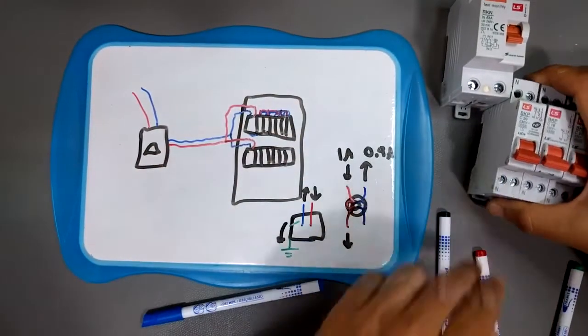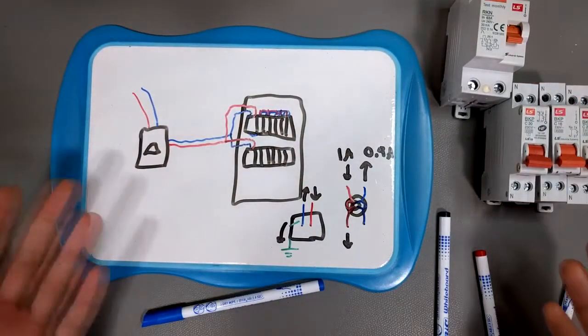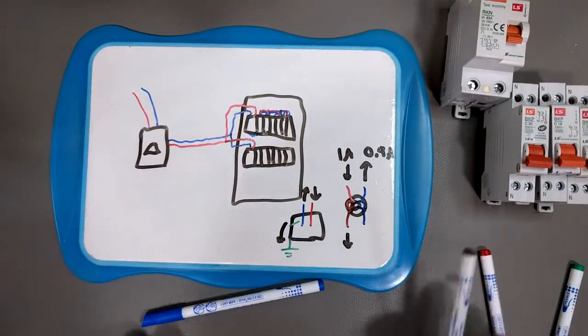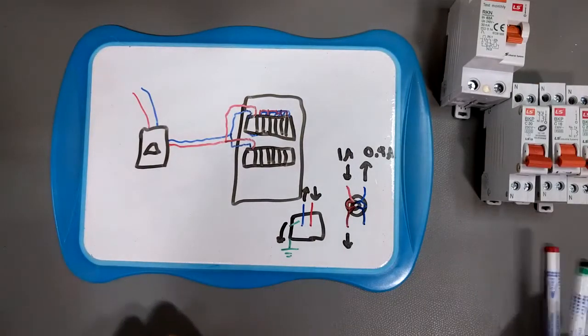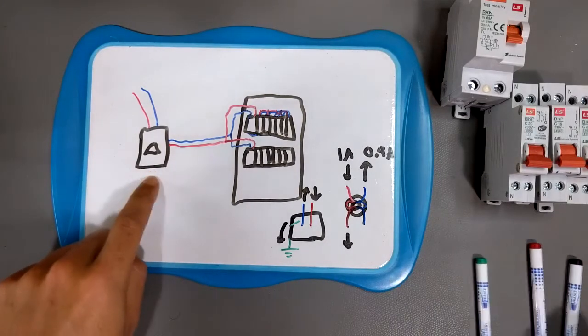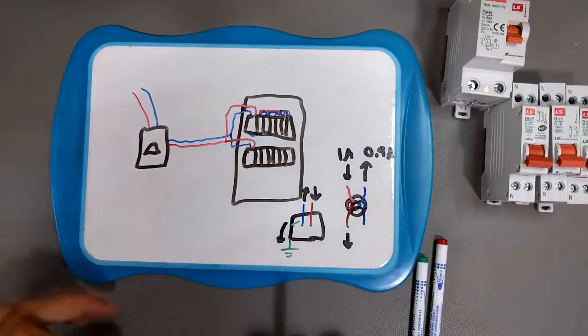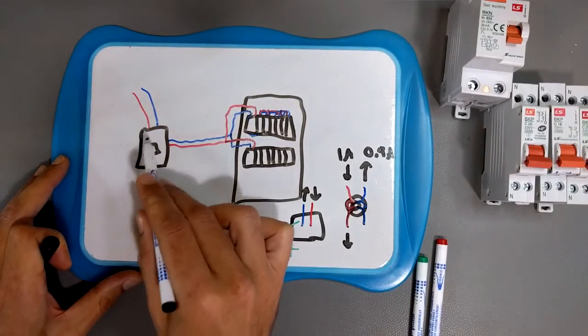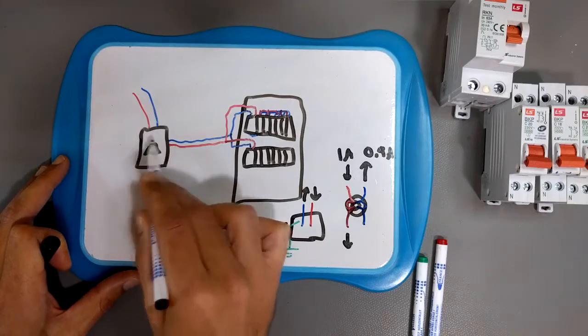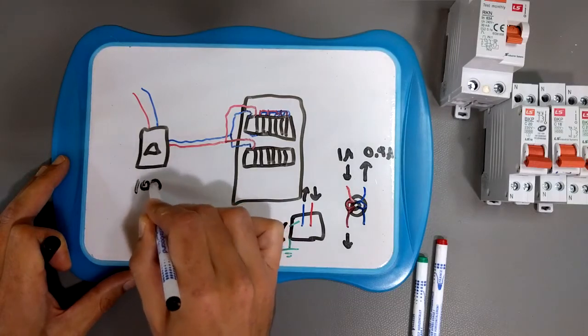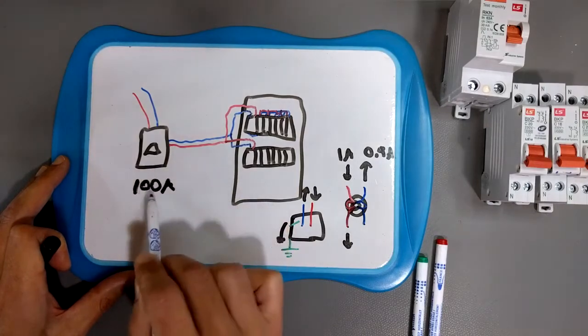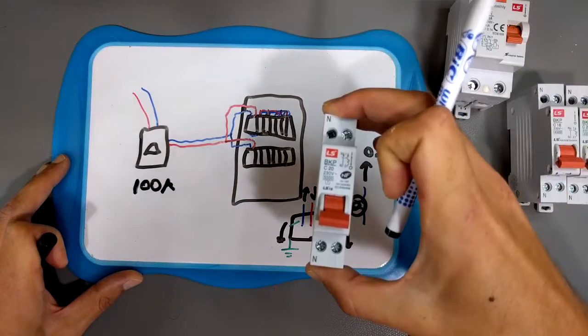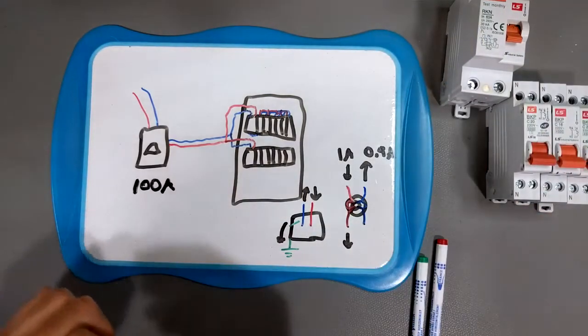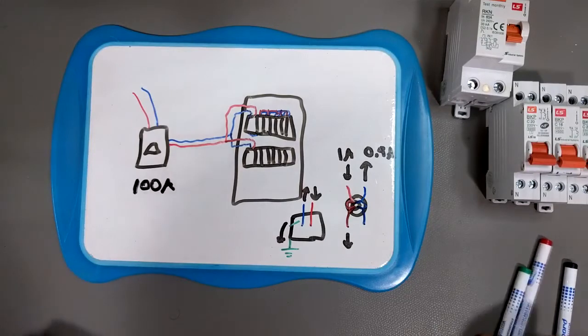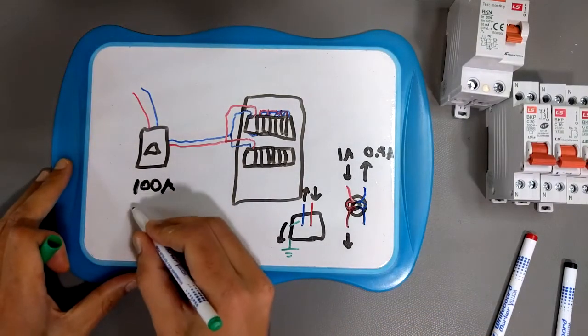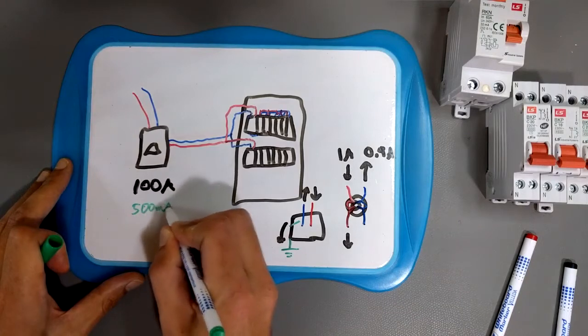But so that's pretty much it. That's what a circuit breaker panel is. So one last thing to note here, you have your main breaker here. This guy actually serves two purposes. Say you have a 100 amp hookup. This main breaker that your electrical company installs, say it's a 100 amp, you have 100 amp service. This main breaker is actually a 100 amp thermomagnetic circuit breaker, more or less, but it's also, and this value varies depending on where you live, say, a 500 mil differential breaker.